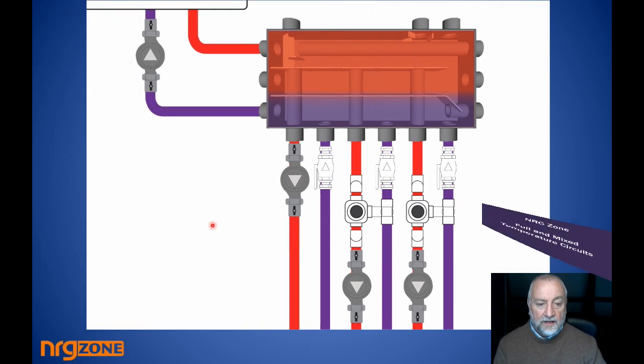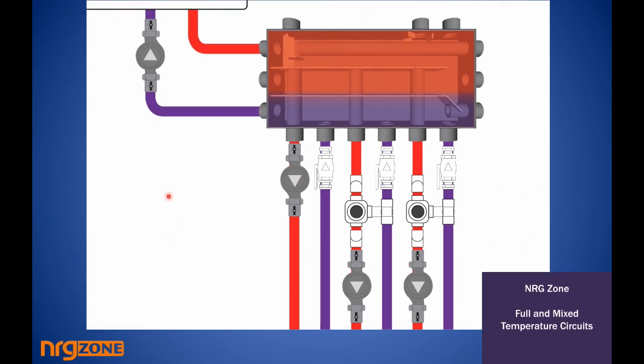Now, again, just showing that if you did have your flow coming in, I did say to you the flow chamber is going to be at its hottest. The heat will drift about, but of course it won't be as hot down here. You've seen that from the flow diagrams a while ago, but as such they would be warmer, whereas the return chamber is this lovely cold water that you're striving for with condensing boilers and heat pumps.